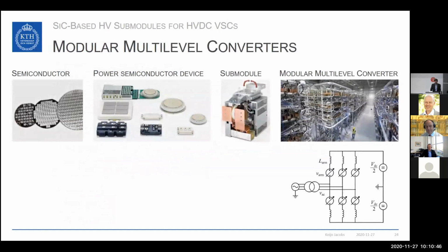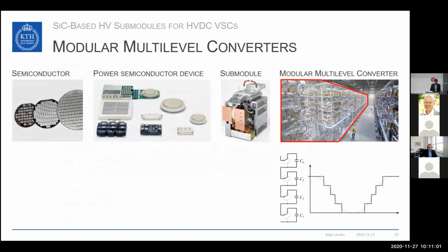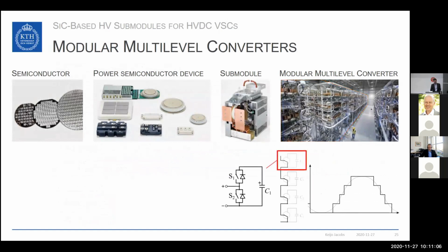A simplified model of the modular multi-level converter can be seen here on the right. I marked a converter arm, and in the equivalent circuit, you can see that one converter arm consists of the arm inductor and a variable voltage source in this model. This variable voltage source models a series connection of submodules. Each of these submodules can either be inserted or bypassed. By doing that, the capacitor of the submodule can either contribute to the arm voltage or not. If we then have a certain amount of these submodules, we can approximate an alternating voltage.